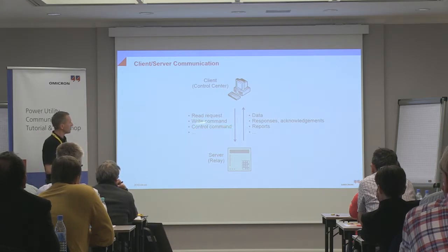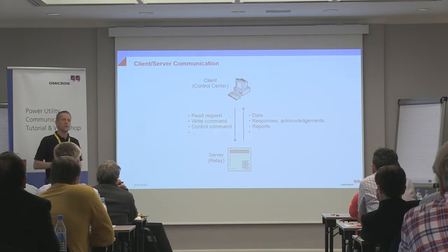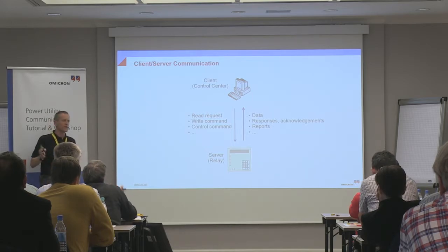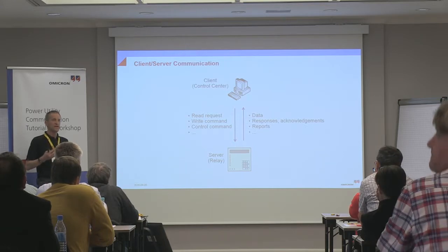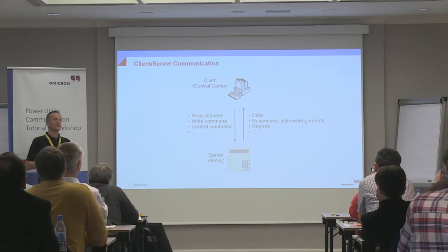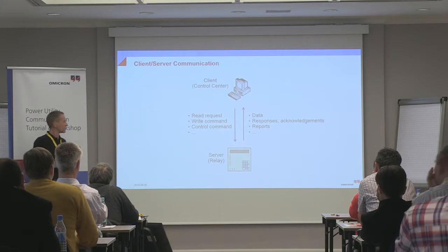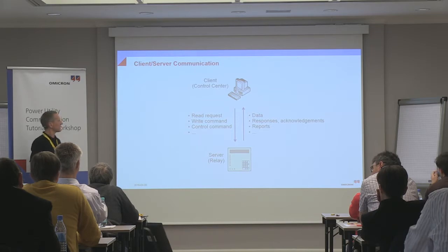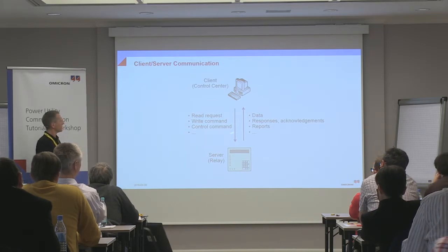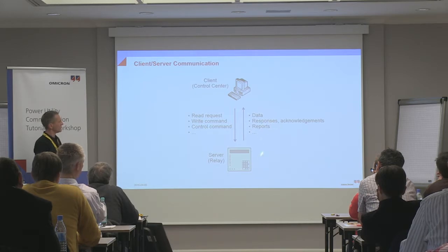And then it can become more complex. You can have complex control sequences. We have already heard about this select before operate. There are many read and write operations involved: first to read the control model, then to write the command value, and then the confirmations to that make up this kind of communication. And of course, the reports, which can be sent from the server to the client.